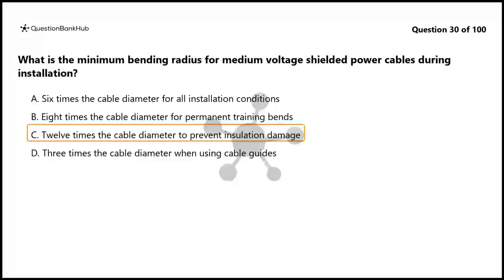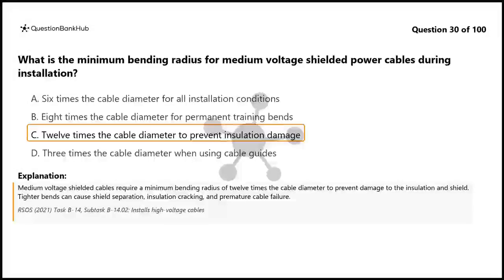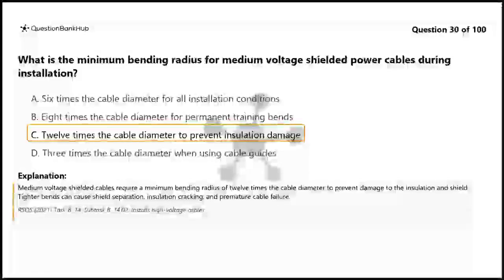The correct answer is C. 12 times the cable diameter to prevent insulation damage. Medium-voltage shielded cables require a minimum bending radius of 12 times the cable diameter to prevent damage to the insulation and shield. Tighter bends can cause shield separation, insulation cracking, and premature cable failure.